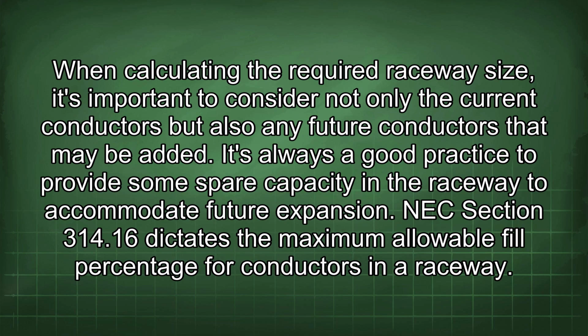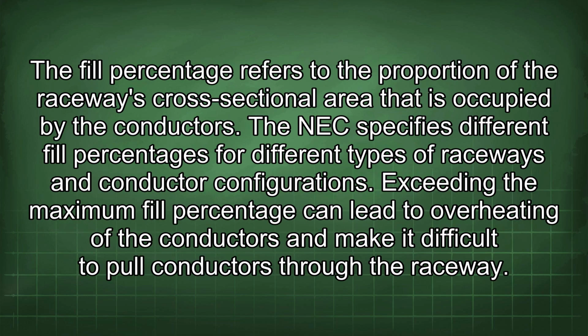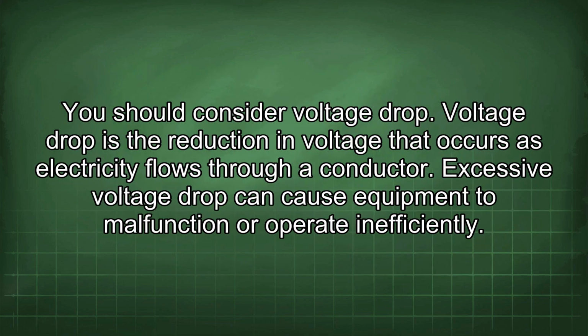It's always a good practice to provide some spare capacity in the raceway to accommodate future expansion. NEC Section 314.16 dictates the maximum allowable fill percentage for conductors in a raceway. The fill percentage refers to the proportion of the raceway's cross-sectional area that is occupied by the conductors. The NEC specifies different fill percentages for different types of raceways and conductor configurations. Exceeding the maximum fill percentage can lead to overheating of the conductors and make it difficult to pull conductors through the raceway. You should consider voltage drop.